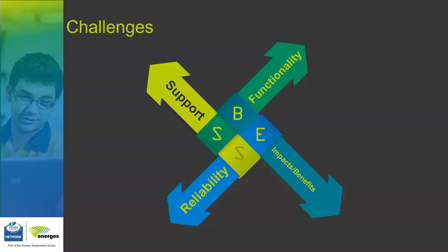What benefit does that bring from a support point of view? When I have a problem or my system trips off, I can send very detailed event files to my manufacturers. Within 12 hours, they've come back to me with the fault. We've picked up the gear we need out of the store and we're heading to site, versus turning up, trying to fault find the problem, then getting on the phone and finding out you didn't bring the right gear. You're back and forward, back and forward, and you start to burn a lot of money. So that remote support is really important, especially when you're talking about the network.